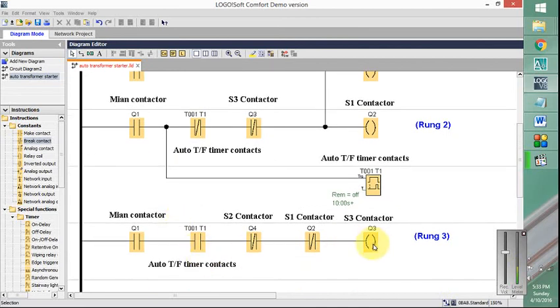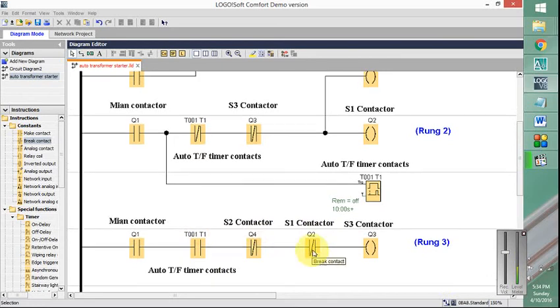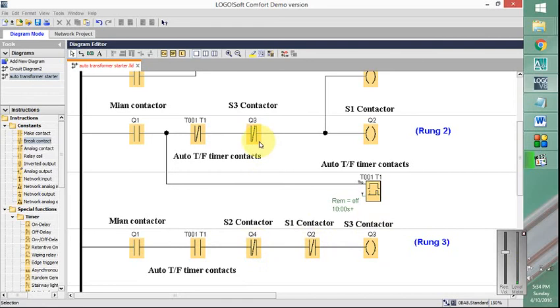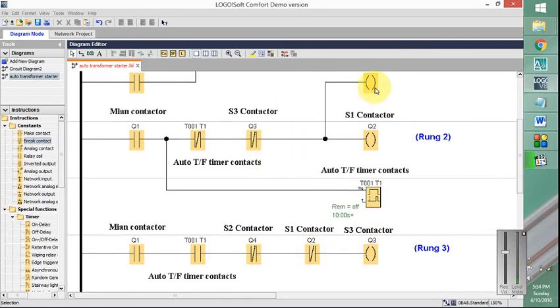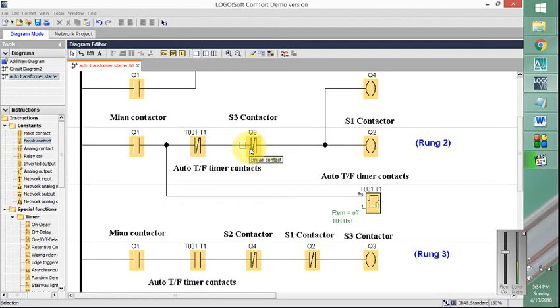And in the third step or the third section, this is the third contactor. So this relay coil will only be energized if main contactor is energized, timer is activated, while S2 and S1 are de-energized. The reason for adding S1 and S2 normally closed contacts here is to prevent simultaneous energizing of all these three coils. So in this way we can prevent the energizing of all these three contactors simultaneously.